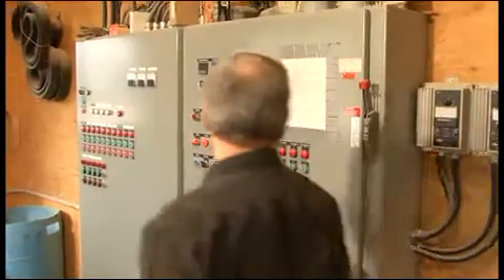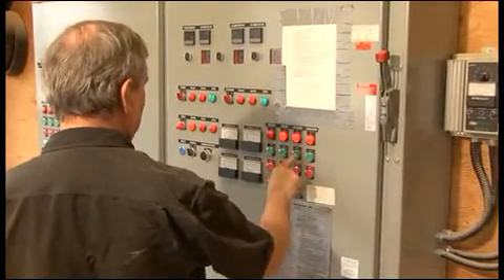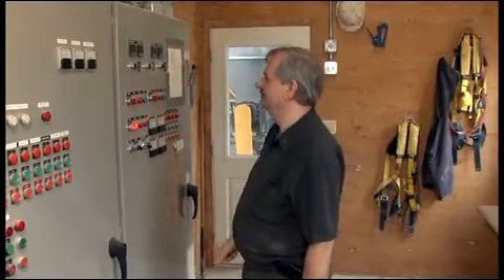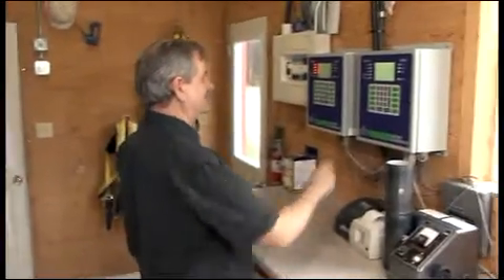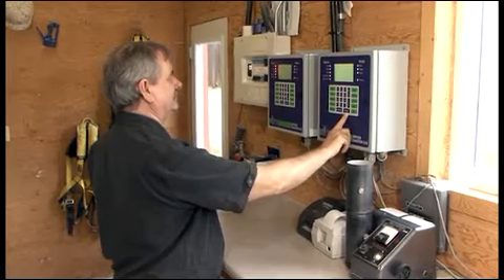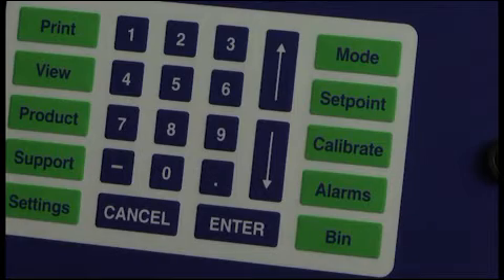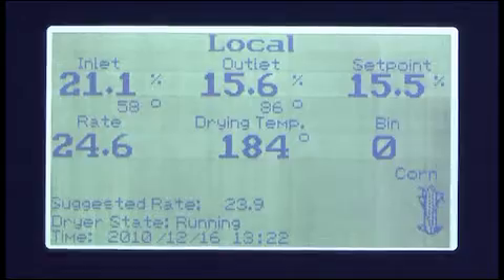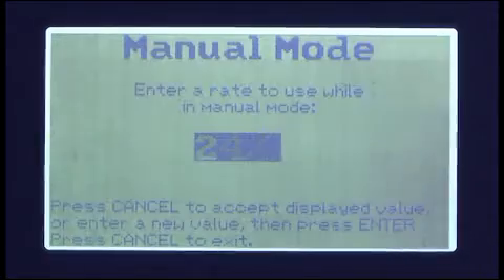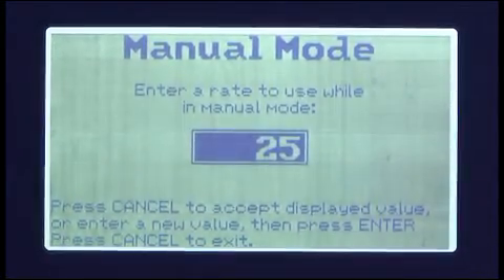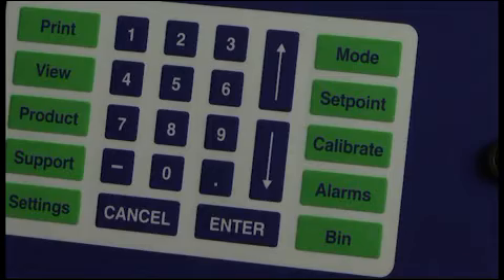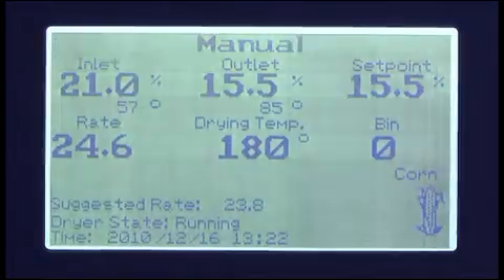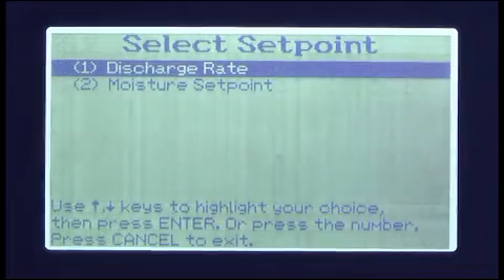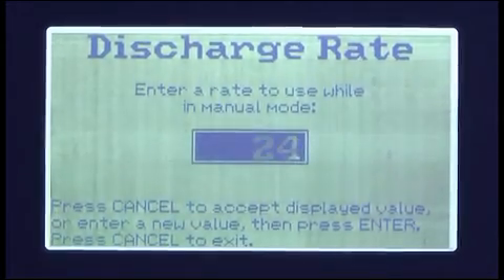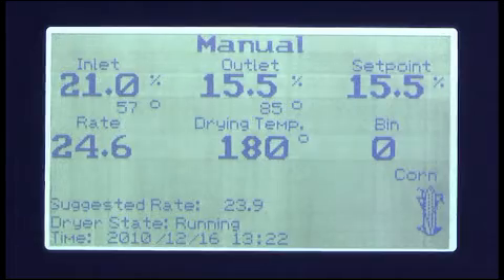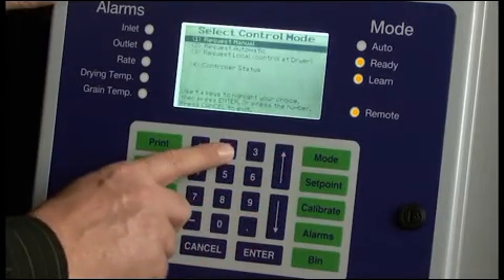Before we finish, let's review a normal daily procedure for operating the Dryer Master. 1. Start your dryer as you have in the past. The Dryer Master panel will likely show that you are in local mode. 2. From the Dryer Master panel, press the Mode button and select Manual Mode and set an initial discharge rate. To change the rate while you are in manual mode, use the Set Point button. Note that you may not be able to switch to manual mode if the Dryer Master indicates the dryer is off. 3. Once the Ready status light is on, press the Mode button and select Auto.